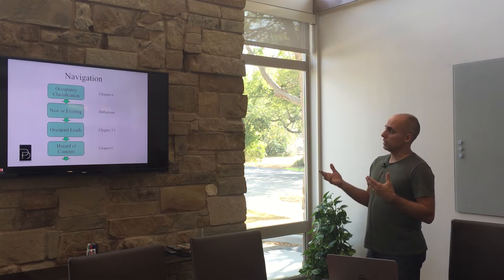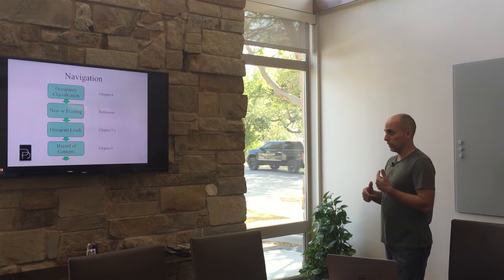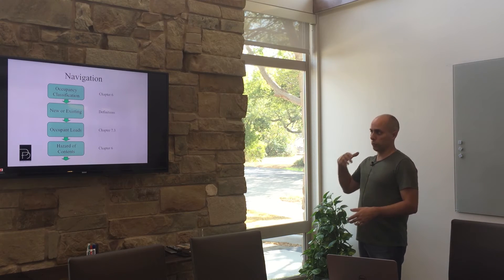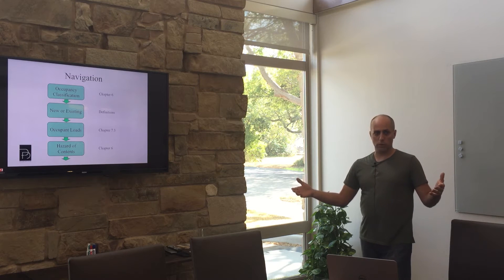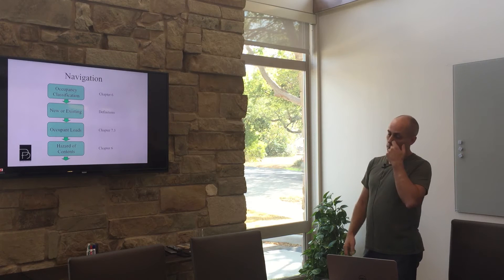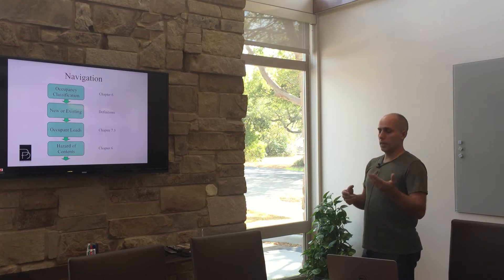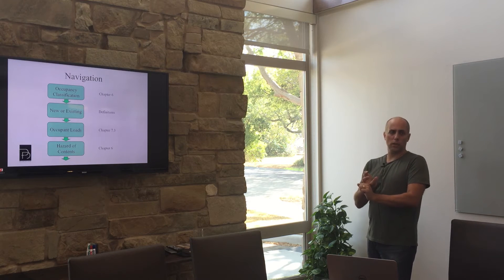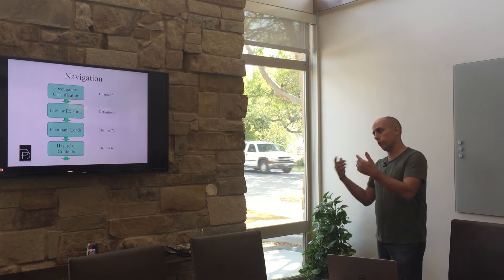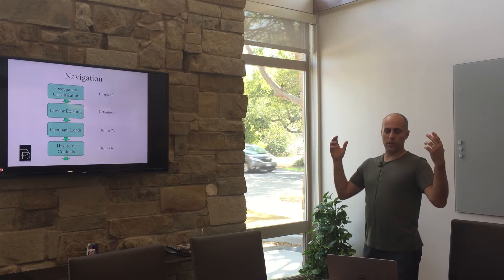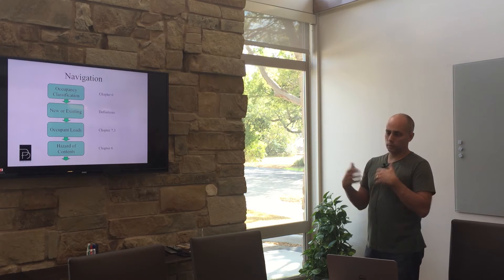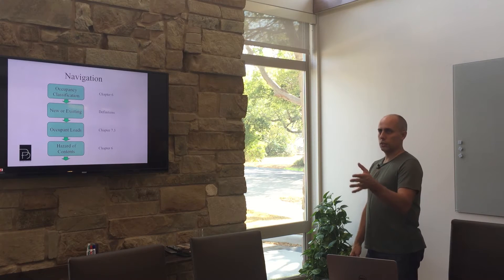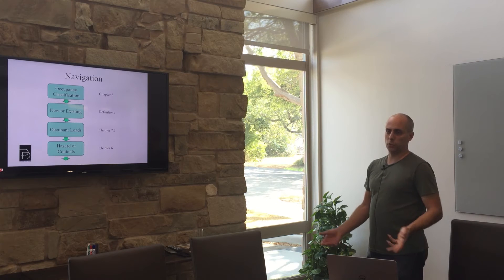After that, you need to determine occupant loads — are you talking about a building for five people or five thousand? That makes a difference for a lot of code requirements. Then determine the hazard of contents, which chapter 6 covers: how high are combustibles, is this a sleeping occupancy, are people there less than 24 hours or longer, is there high-pile hazardous storage, or is it an aircraft hangar? The hazard of contents generally correlates with the occupancy classification, which is why they're under the same chapter.